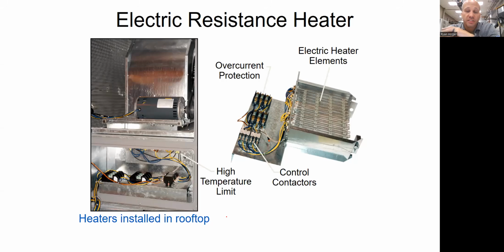If you have electric resistance heat, then obviously you will not see a gas line to the unit, right? And you'll see regular stuff like electrical wiring, but that doesn't mean there's electric heat. It could be a cooling only or a heat pump. It's probably not a heat pump, and it's not likely to be cooling only either. So it probably does have electric heat, but to be sure, when you open up that unit, you will see tons of fuses in there, right? Instead of just a couple fuses for the fan and the compressor, you'll see fuses for all these individual heaters.